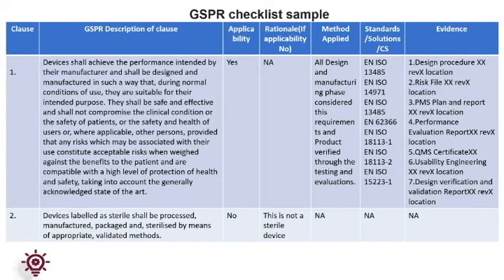The GSPR is part of the technical documentation that should be submitted to the notified body to pursue certification. For demonstration of conformity, we first need to assess the applicability of the GSPR checklist. If applicable, we provide the relevant document and reference sources. If not applicable, we give a justification stating why. Then the method to demonstrate compliance is noted. For applicable standards or common specifications, the relevant harmonized standard or common specification is cited, and the relevant document with revision or version number must be mapped, with cross-reference locations of such evidence shared.